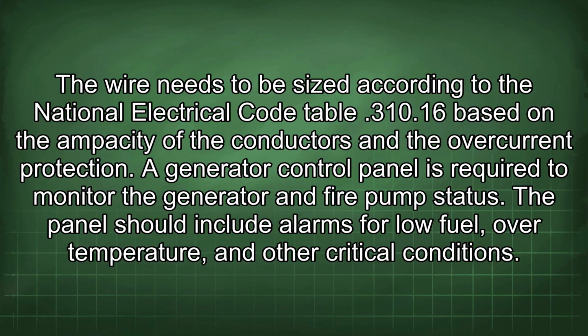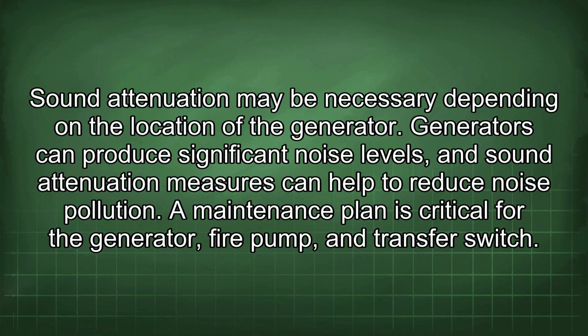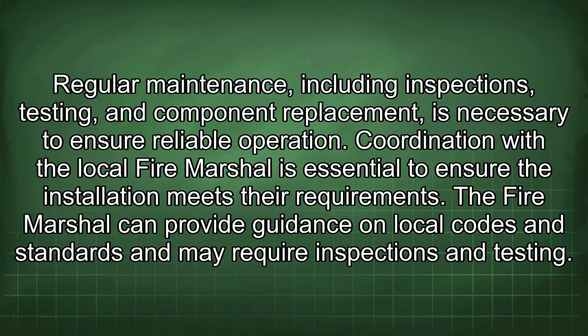A generator control panel is required to monitor the generator and fire pump status. The panel should include alarms for low fuel, over temperature, and other critical conditions. Sound attenuation may be necessary depending on the location of the generator. Generators can produce significant noise levels, and sound attenuation measures can help to reduce noise pollution. A maintenance plan is critical for the generator, fire pump, and transfer switch. Regular maintenance, including inspections, testing, and component replacement, is necessary to ensure reliable operation.